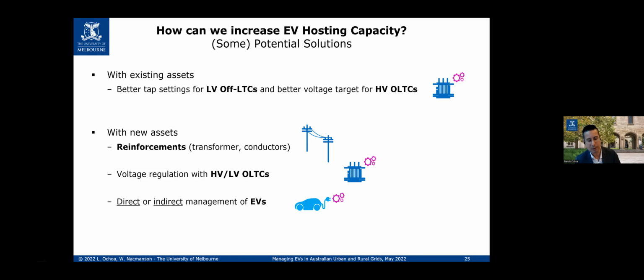What can you do? Well, replace your assets. You can reinforce or augment them, as it's also known—larger conductors and larger transformers. That's quite expensive and time consuming, but it's an option. We can also do voltage regulation with new types of transformers, such as on-load tap changers in the distribution transformers. Expensive to replace as well, like for like, but it's an option. Or we could potentially directly or indirectly manage electric vehicles.